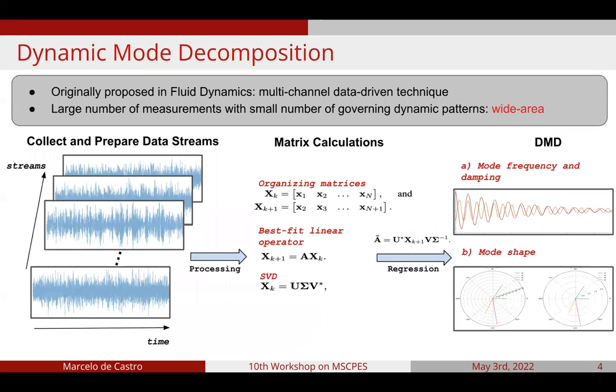So dynamic mode decomposition is a technique first proposed in fluid dynamics that allow us to use multi-channel data in order to perform modal analysis, such as the one described previously. It is extremely useful when there is a large number of measurements with small number of governing dynamic patterns. This is good because this is exactly the case for wide area modes which are observed in power systems.